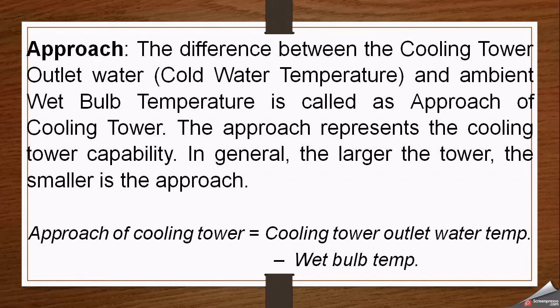Another important term in the cooling tower is approach. The approach is defined as the difference between the cooling tower outlet water temperature — the cold water temperature after passing through the cooling process — and the ambient wet bulb temperature. This difference between the wet bulb temperature of the atmosphere and the cold water temperature coming out of the cooling tower is equal to the approach.